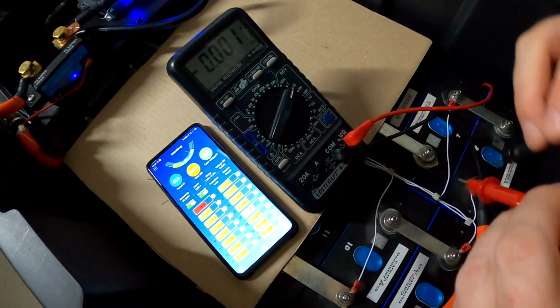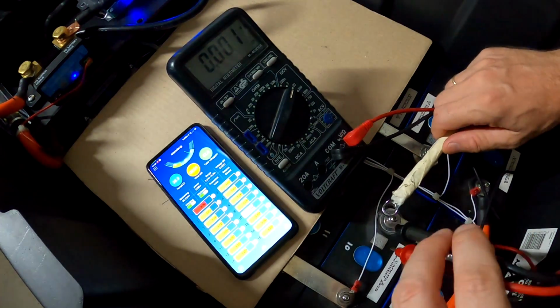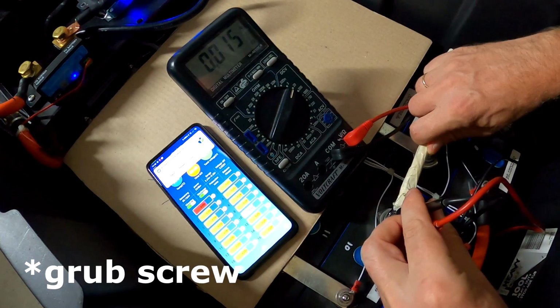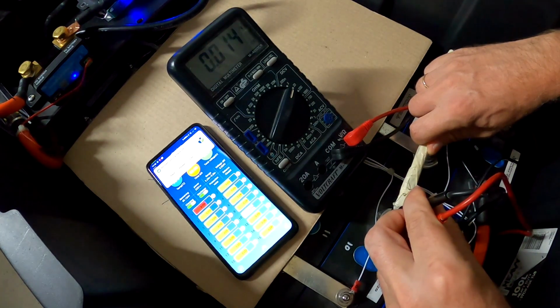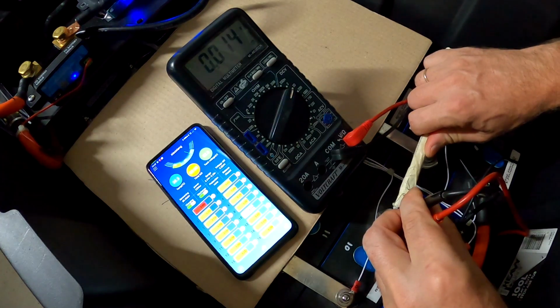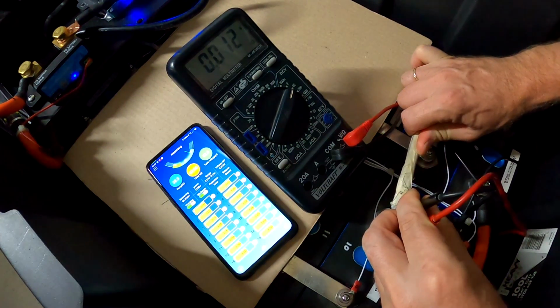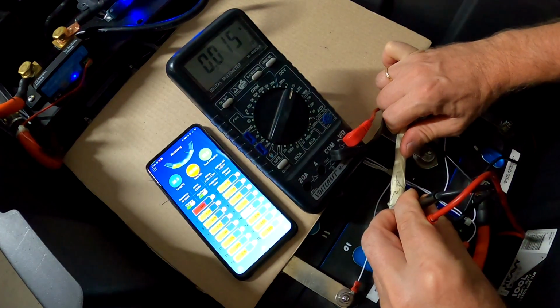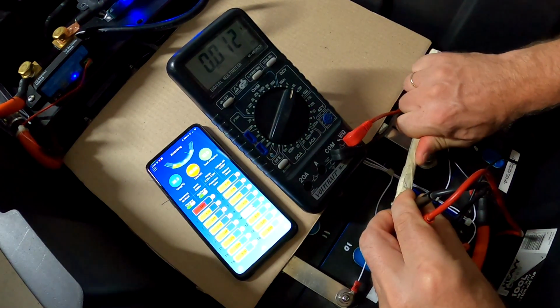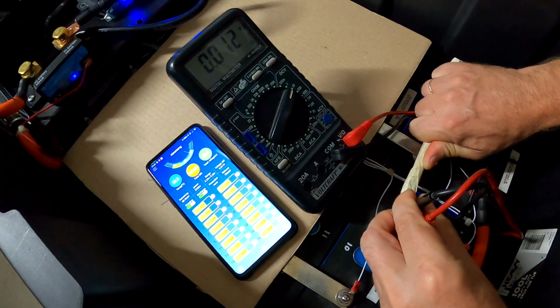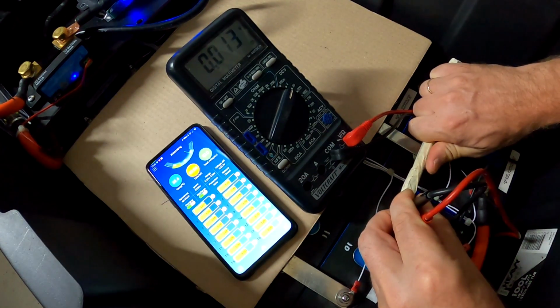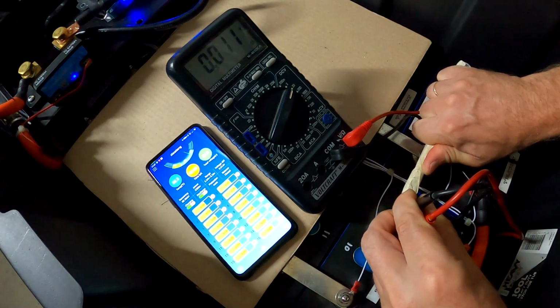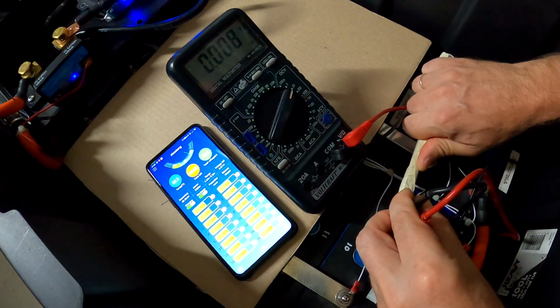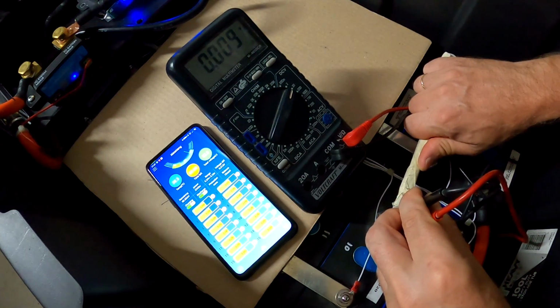Okay, so I will get my spanner here, and we put the voltmeter back on the grub nut and the bus bar, so you can see on the multimeter the 15 millivolt, and I just loosen this nut a little bit. Nothing changes, and now I'm tightening it again, and now we've got only 10 millivolt difference, so I'm not sure how far I can tighten that. 8. So it goes a little bit down.